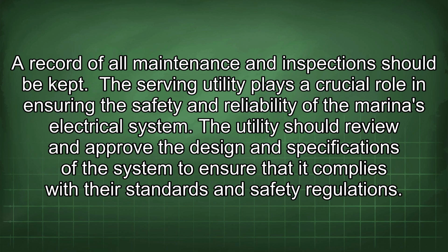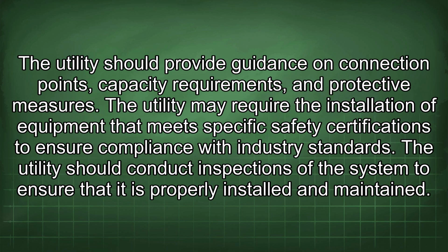The serving utility plays a crucial role in ensuring the safety and reliability of the marina's electrical system. The utility should review and approve the design and specifications of the system to ensure that it complies with their standards and safety regulations. The utility should provide guidance on connection points, capacity requirements, and protective measures. The utility may require the installation of equipment that meets specific safety certifications to ensure compliance with industry standards. The utility should conduct inspections of the system to ensure that it is properly installed and maintained.